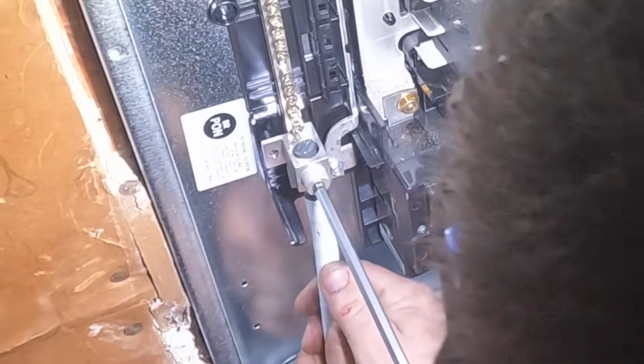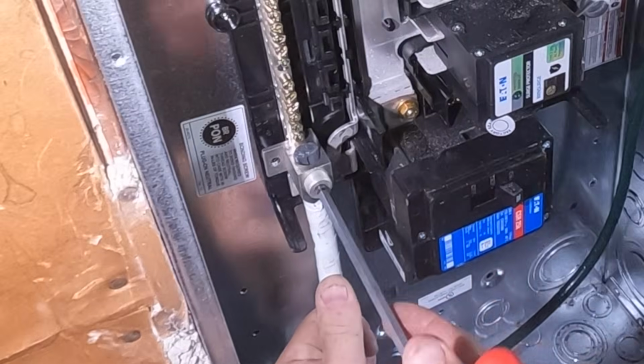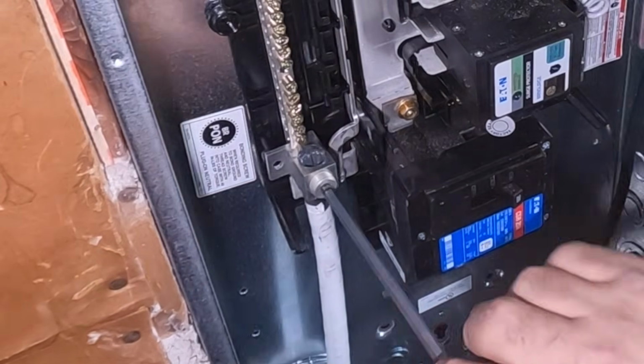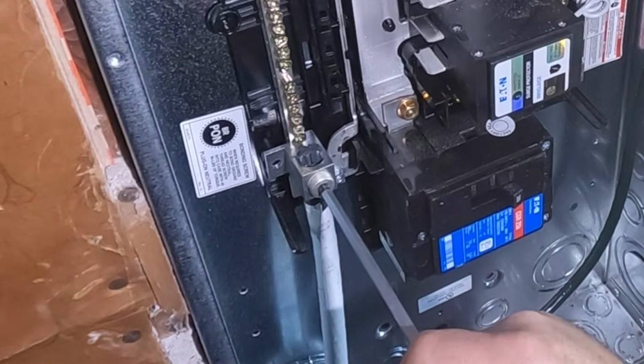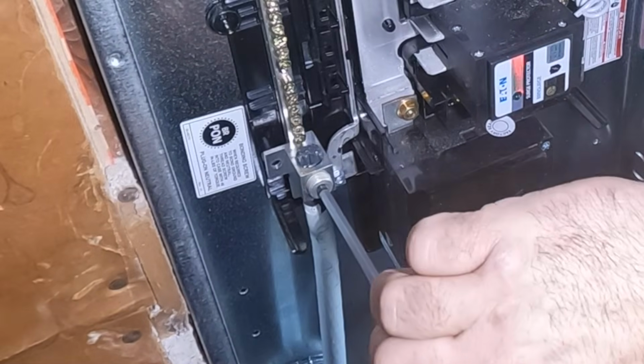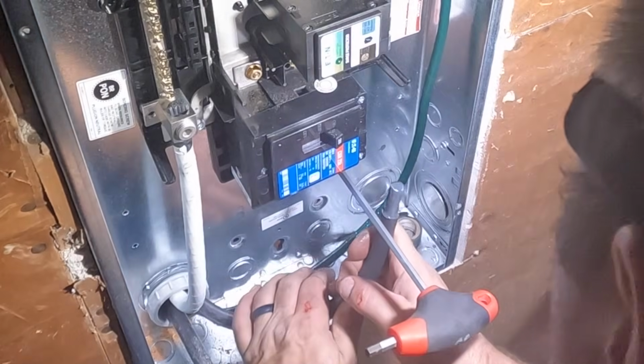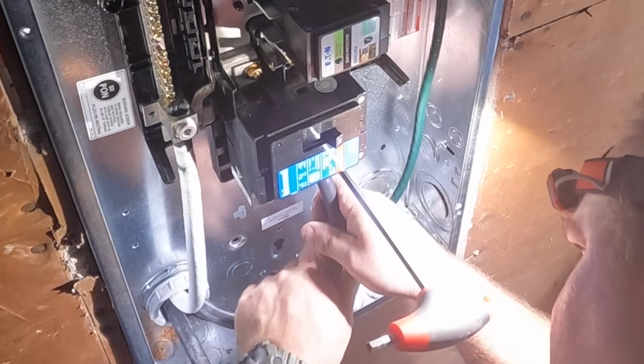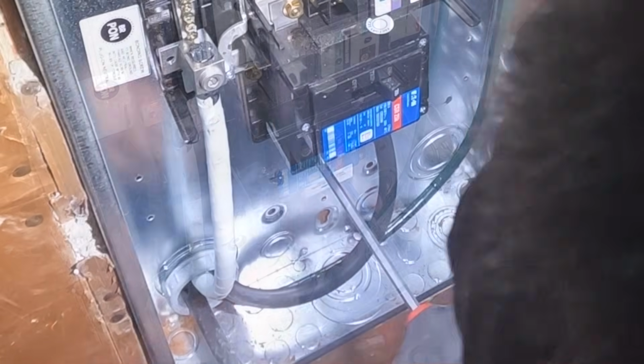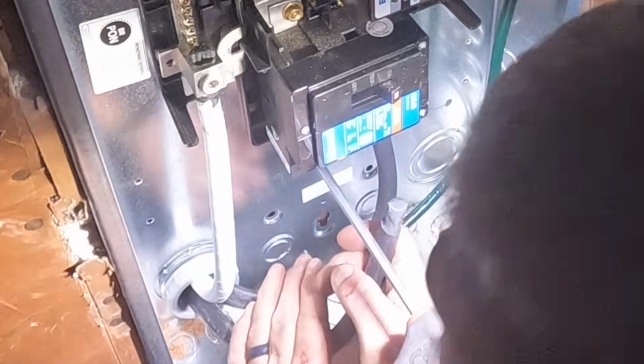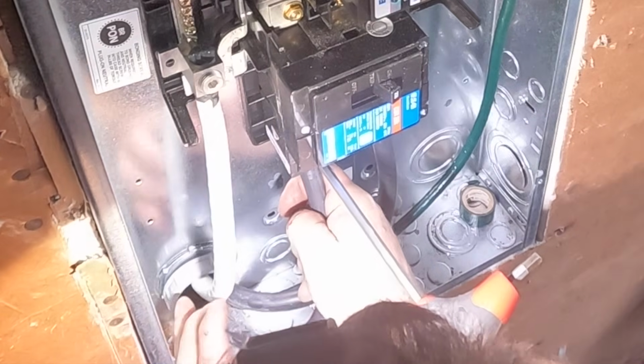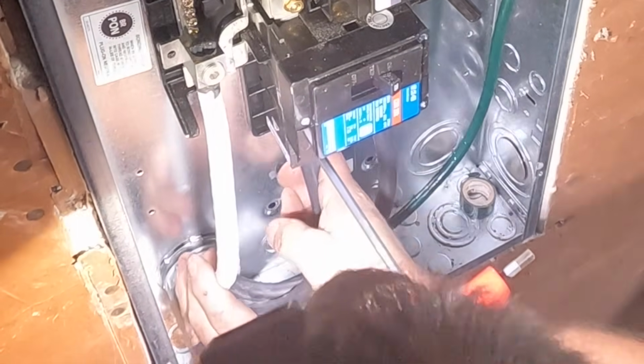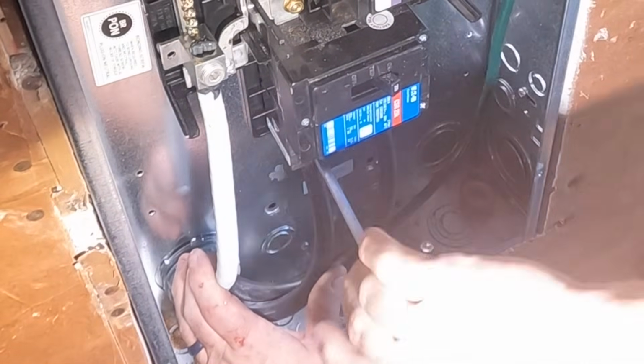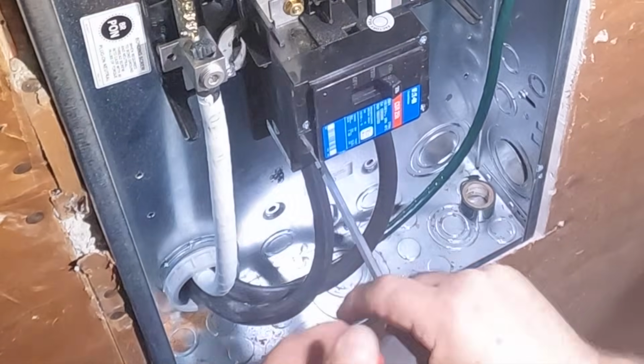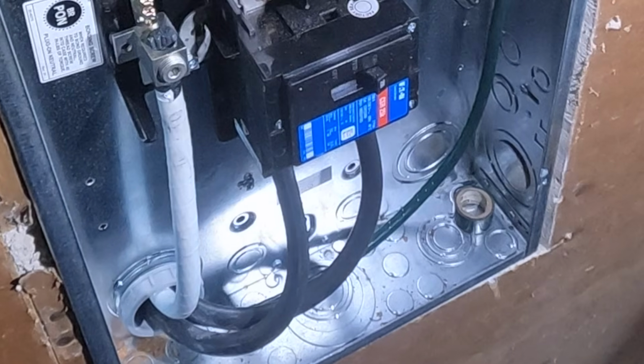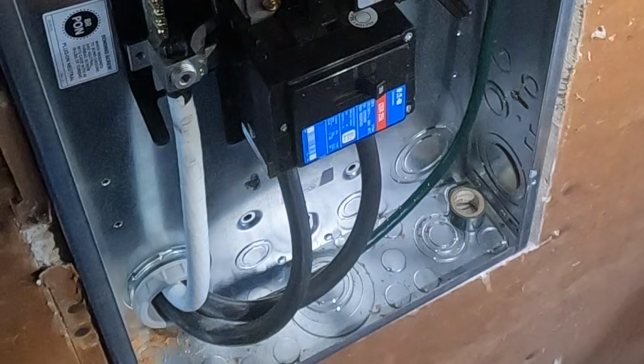This is also my main lug only panel here. And so this jumps out from one side of the neutral terminals to the other side of neutral terminals, making all my grounded neutral connections return to the source through the main disconnect and eventually back through that bare wire from the service drop. It's also important to note that you want to do the meter main terminations on the outside because there's less working space than there is here in this main breaker panel, which is why I terminate these last.